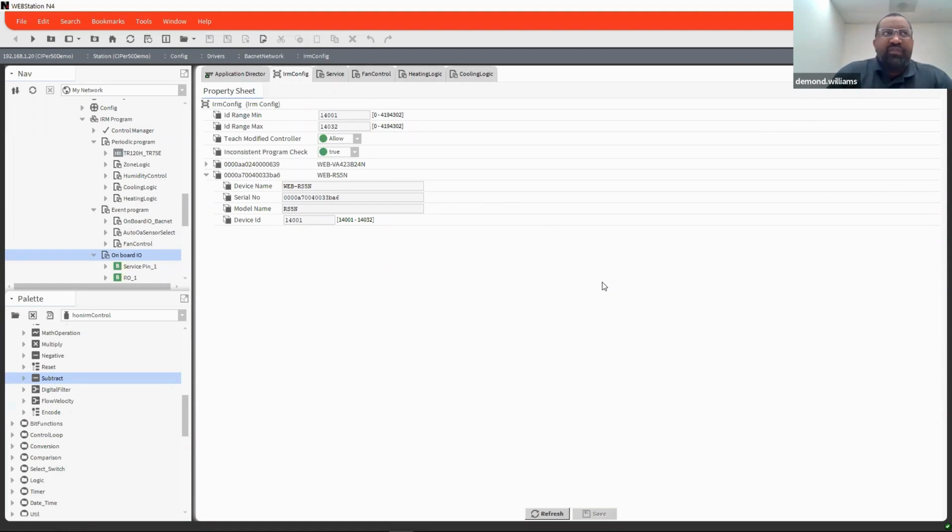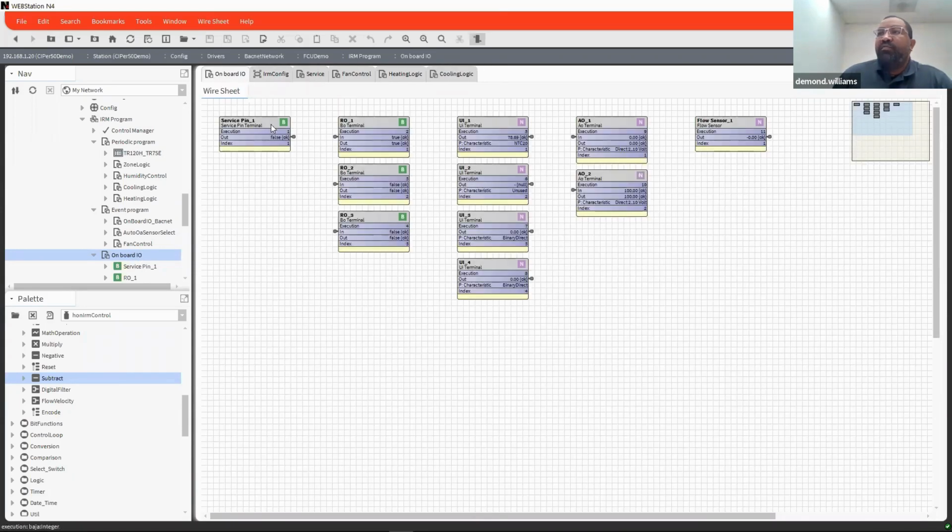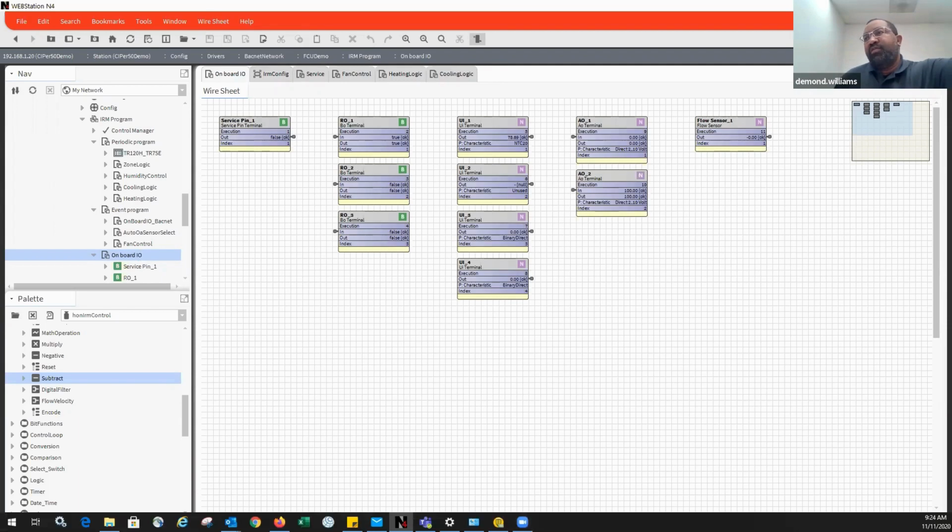So like I said, wiping the controller is basically a combination of powering down your controller and powering it up while holding the button. To do the config here, to pull it into a property sheet to list out all your controllers, is a momentary push. And then back here on the onboard IO, you have to hold it down for a few seconds, and then it officially switches.